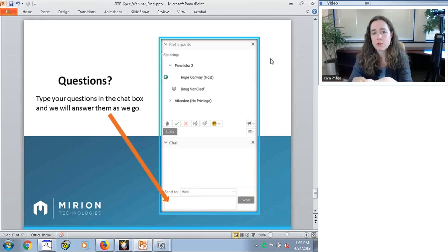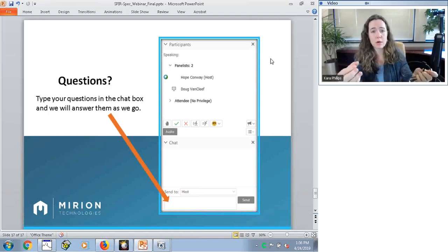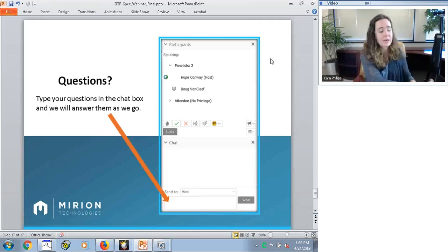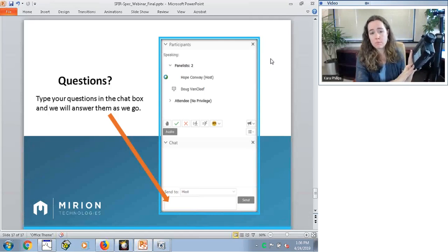What you would do is you'd create the calibration, for instance the drum calibration on your computer, and then you make what we call a Genie CAL file. Then you'll use your same USB cord here to actually load it back into the SPIR-Ace and put it within a specific location in the SPIR directory. And then that geometry becomes available as an option. So the answer is yes, you can do both ways.